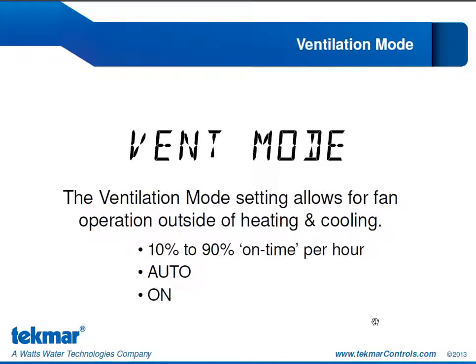Our ventilation mode allows us to configure the fan operation to work outside of heating and cooling if that's what we want. So we can configure the ventilation for 10 to 90% of on time per hour, where each 10% is equal to 6 minutes of on time for that hour. We can put it into auto mode, where it will run only during heating and cooling, or we can turn it on, in which it's on 100% of the time. So ventilation is also known as intermittent fan, if you're more familiar with that term.